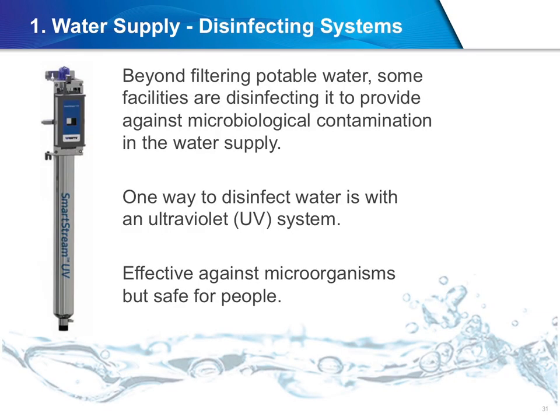With any uncertainty over the quality of the water entering a building, many healthcare facilities are being proactive and using a centralized system to at least filter, if not fully disinfect, the incoming water. Of particular relevance is an ultraviolet disinfection system, which is highly effective at providing protection against microbiological contamination in water. These systems are attractive not only because they can be very effective at killing microorganisms such as Legionella bacteria, but also because they are fairly simple to use and operate.